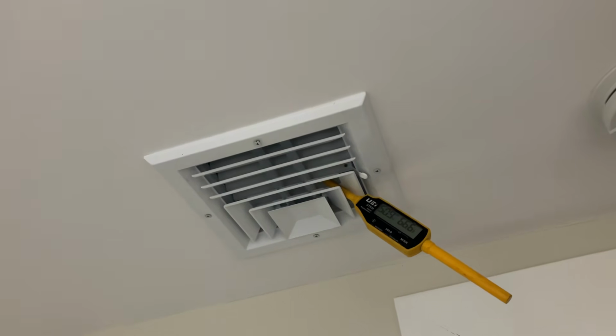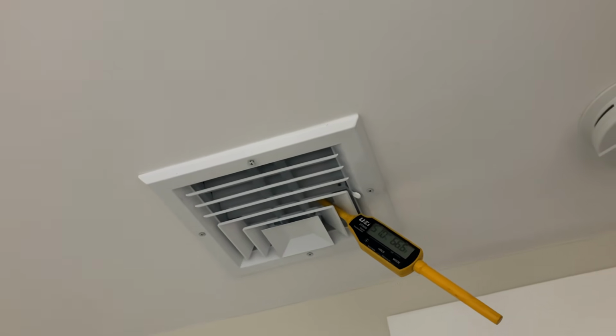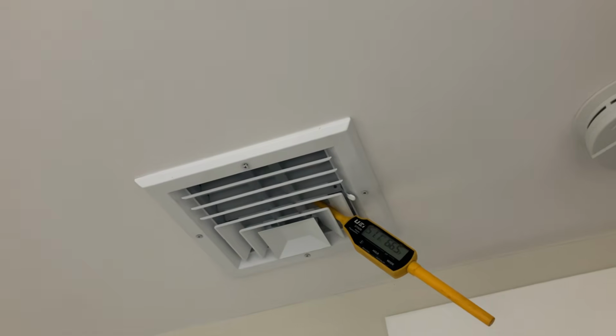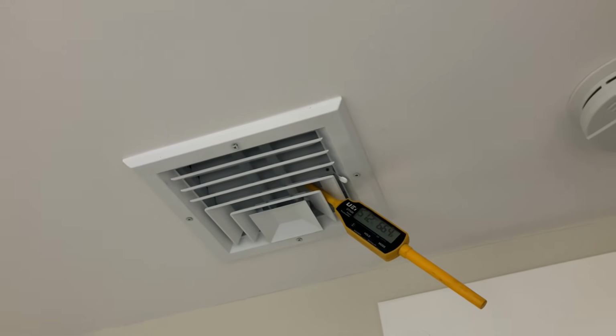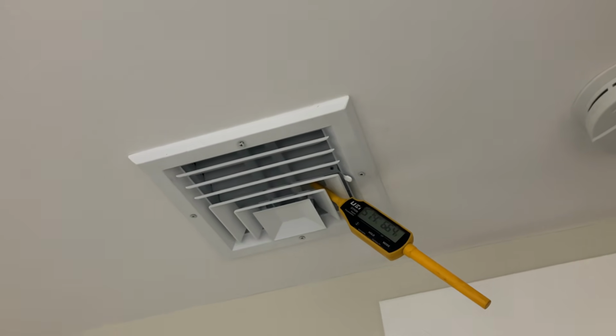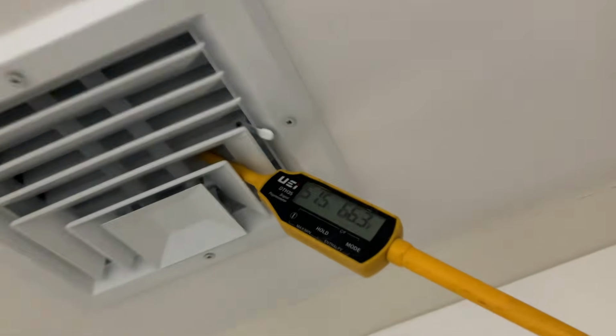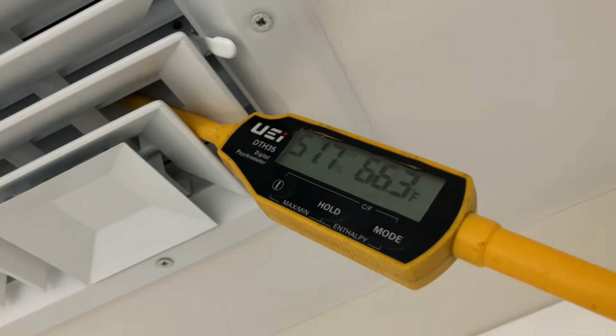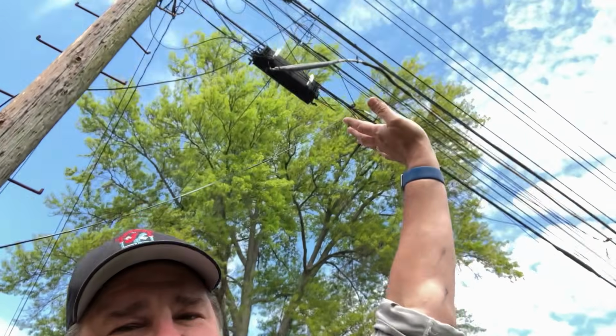We got a 4-ton system for a 1,200 square foot house. Let's check our temperatures and pressures of the refrigerant, because I need a 15-degree delta T minimum with this grossly oversized system. All right, head downstairs, and as I'm walking out the door, the abuela is up like this at the vent. She goes, "It's working." And I go, "It's functional, but it could be better."